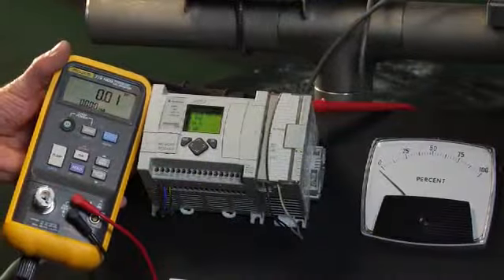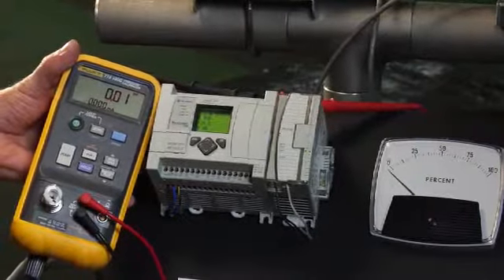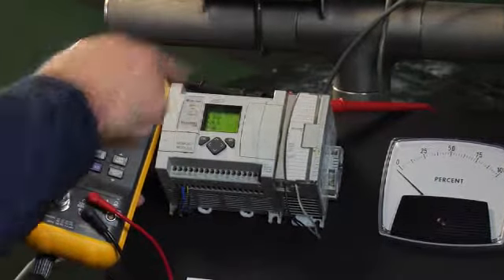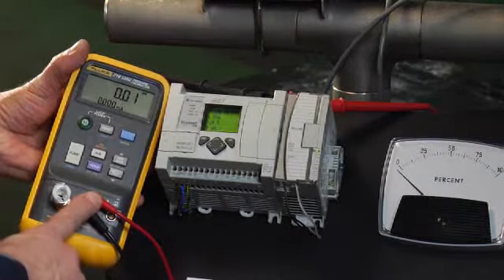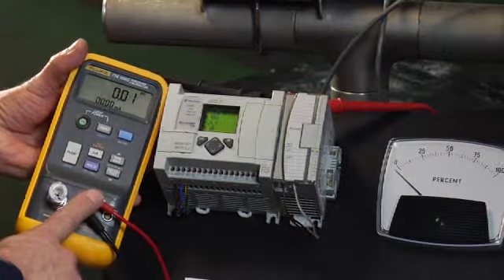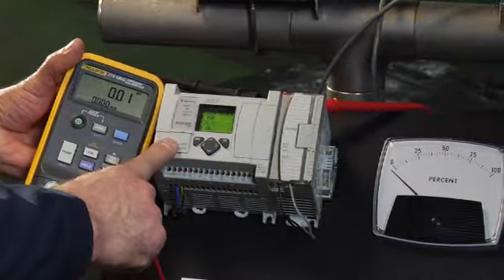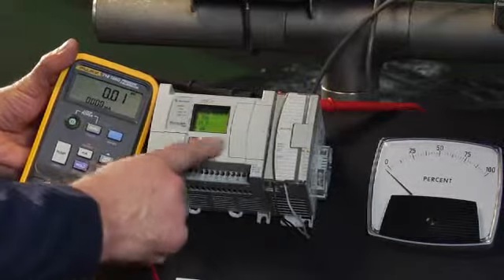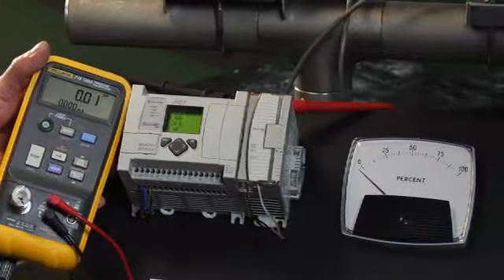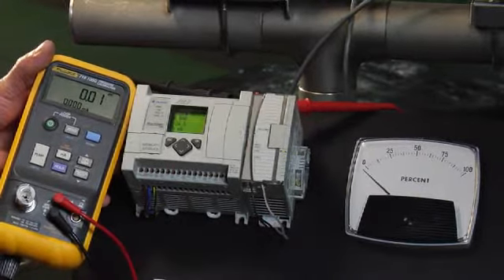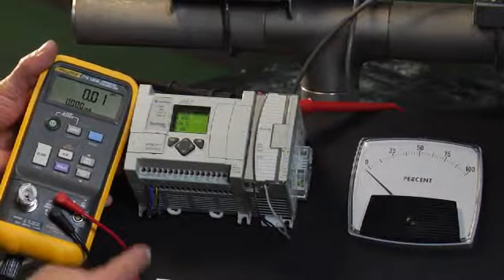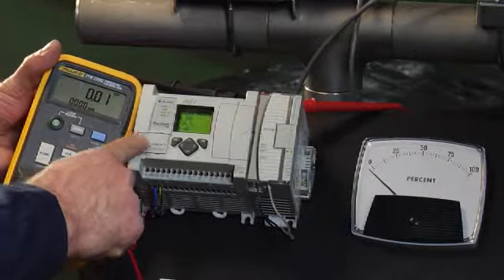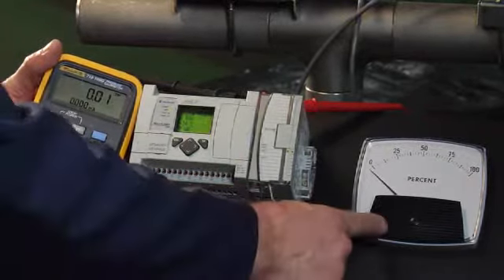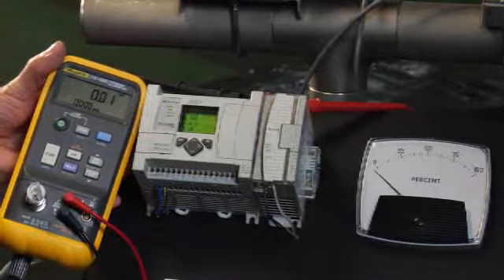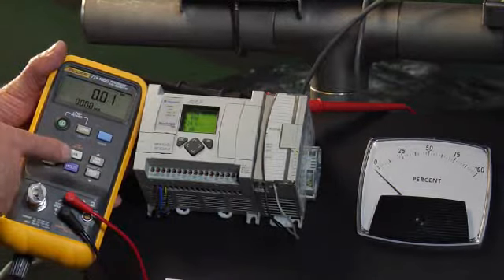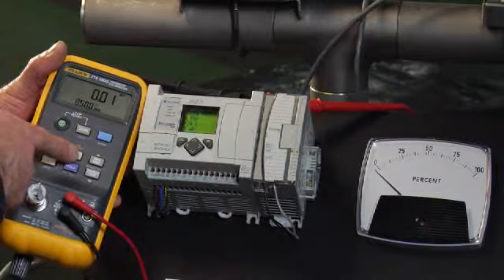In this example, we have the 719 milliamp output connected on the input of the PLC. We'll drive the milliamp signal from the output of the 719 into the PLC, which then produces an output signal to drive a local indicator. By sourcing a milliamp signal, we can test the input of the PLC, the output of the PLC, and the local indicator. To perform this test, toggle the milliamp output mode to source.